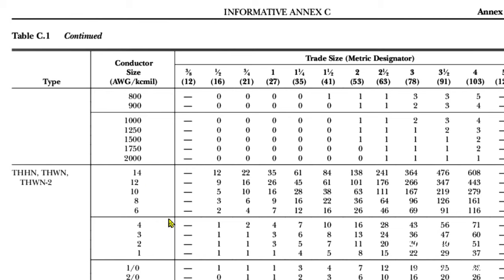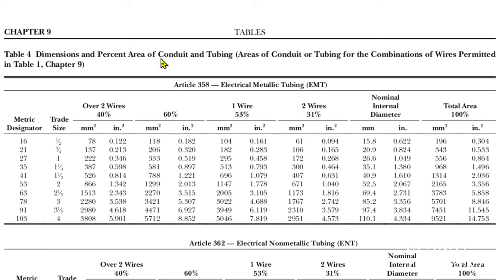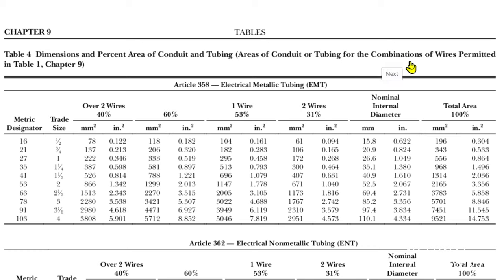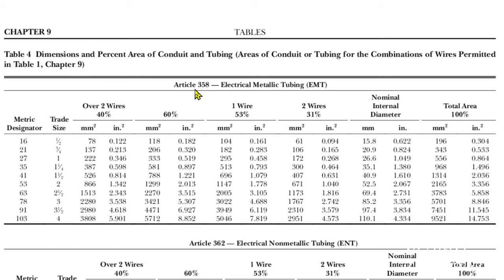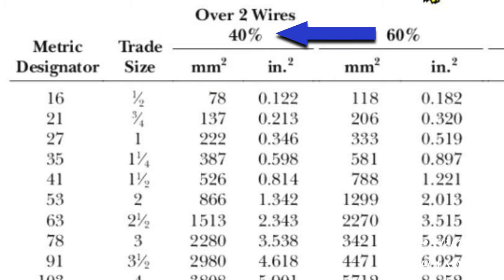So let's go to a different table to help us out. So here we are now at Chapter 9, Table 4, and this one's about dimensions and percent area of conduit and tubing. That is areas of conduit or tubing for the combinations of wires permitted in Table 1, Chapter 9. And this is Article 358, Electrical Metallic Tubing.